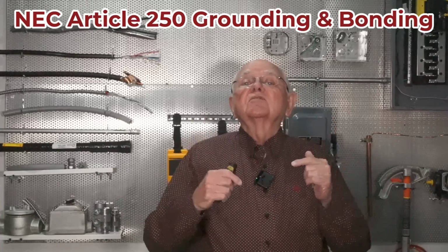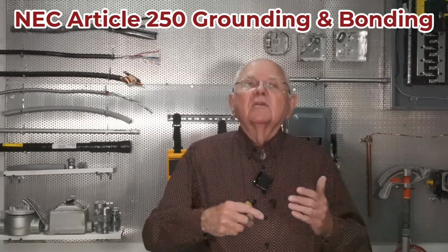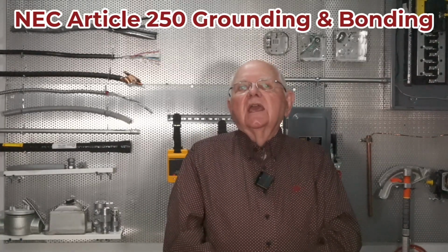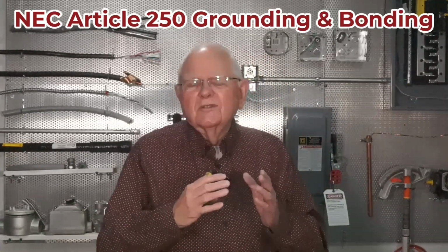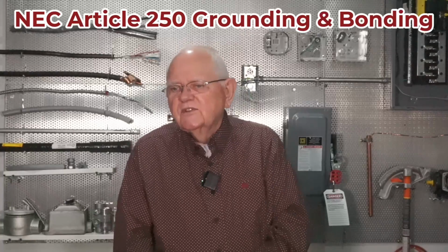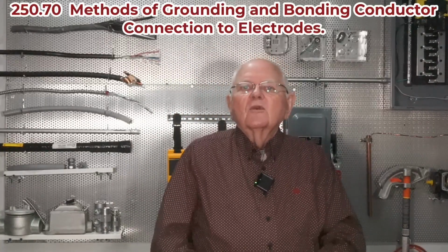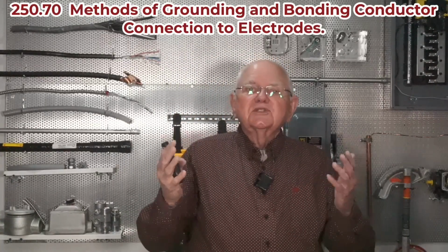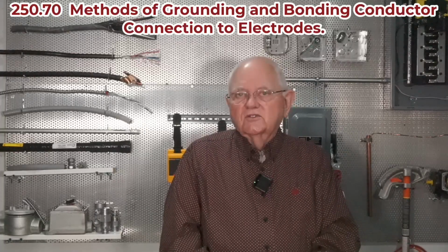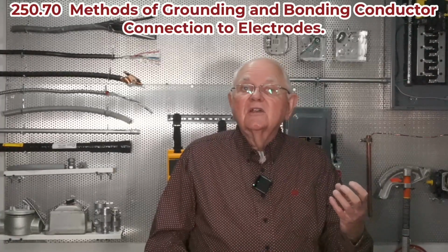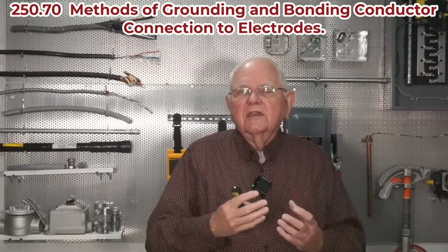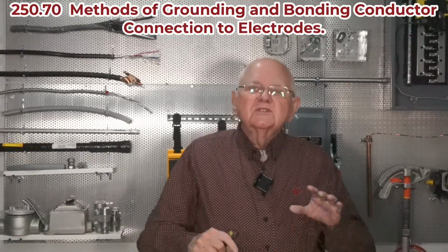When it comes to connecting grounding electrodes, using the water pipe as your grounding electrode system, it also mentions in the NEC, and this was a discussion point over the last few years with 250.70, where it says my ground clamps shall be listed for the materials of the grounding electrode. And so if I'm going to a galvanized water pipe and I have a copper grounding electrode conductor, and going to a copper ground rod, make sure that the listings on your clamps are applicable to whatever type of material that you're going to.